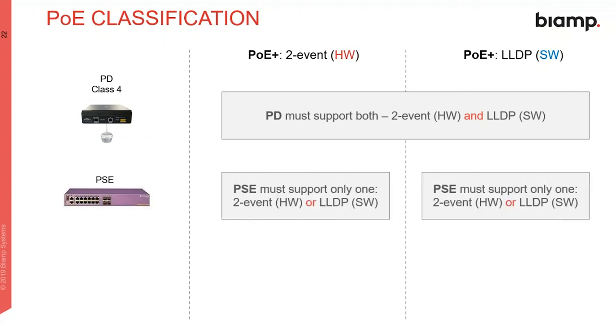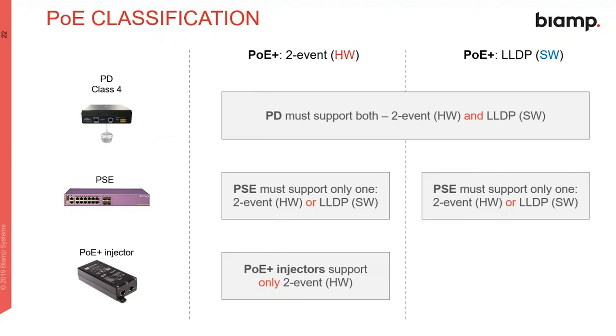However, the power sourcing equipment, so your switch or your midspan—most midspans, it depends on whether it's going to support LLDP or not—but they only support one. So it's going to support either the two-event hardware or LLDP to be able to get the PoE Plus working. So it's important to know which one your PSE uses and to make sure it's enabled. Check your switch's documentation if you're using a switch. Your PoE injectors and the majority of your midspans just use the hardware negotiation method.